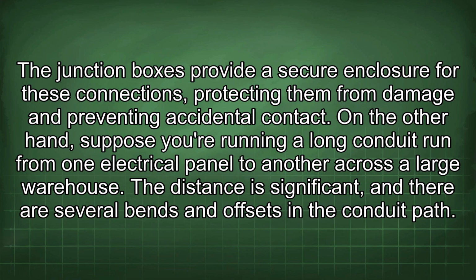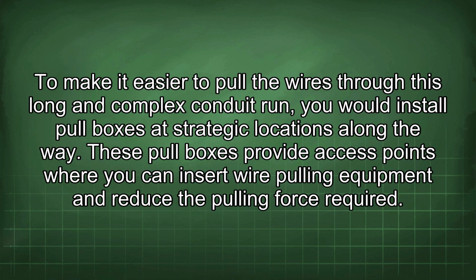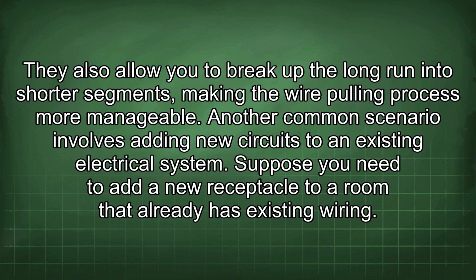On the other hand, suppose you're running a long conduit run from one electrical panel to another across a large warehouse. The distance is significant, and there are several bends and offsets in the conduit path. To make it easier to pull the wires through this long and complex conduit run, you would install pull boxes at strategic locations along the way. These pull boxes provide access points where you can insert wire pulling equipment and reduce the pulling force required. They also allow you to break up the long run into shorter segments, making the wire pulling process more manageable.